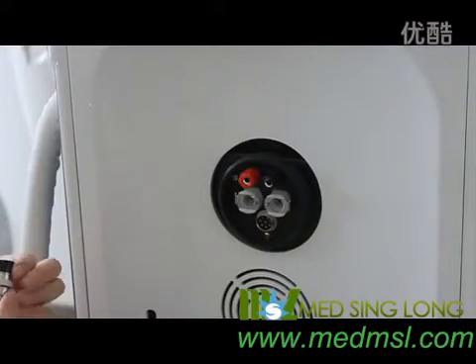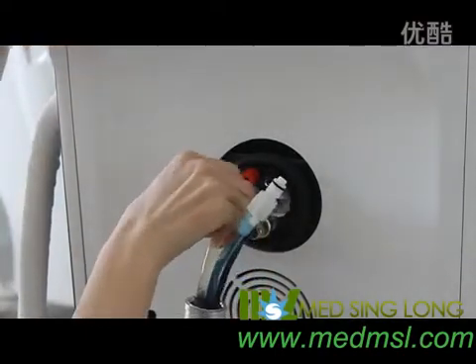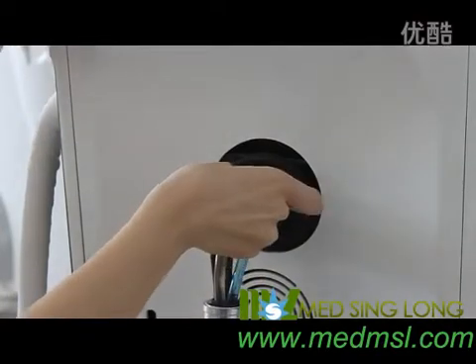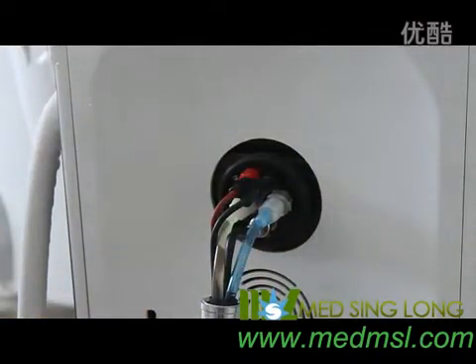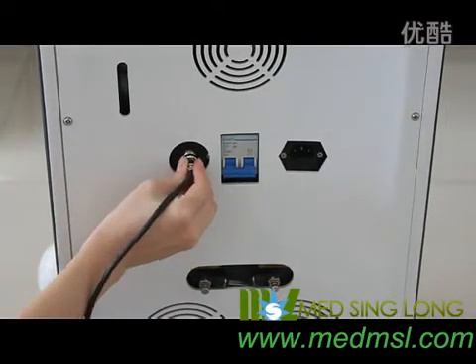After adding water, we will show how to connect the handpiece. First, the ground wire. Then the two corresponding water tubes. At last, the high voltage wires. Finally, insert the foot switch.